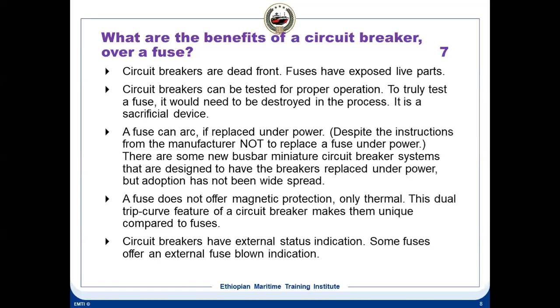It's only thermal. And this dual trip curve feature of a circuit breaker makes them unique compared with the fuses. That's another advantage of circuit breaker. It's a magnetic protection. Fuse is a thermal protection. Circuit breakers have got external indications, whether it is open or closed, you have indications. Fuse, you have no indications. Some of the fuses have got blown indications. On top of the fuse, you'll have an indication which indicates the fuse is blown or not. So these are the benefits of a circuit breaker over a fuse. Okay. And a circuit breaker can be used like a switch. It can be switched on and off many times.